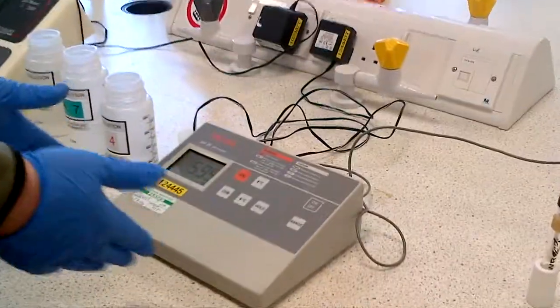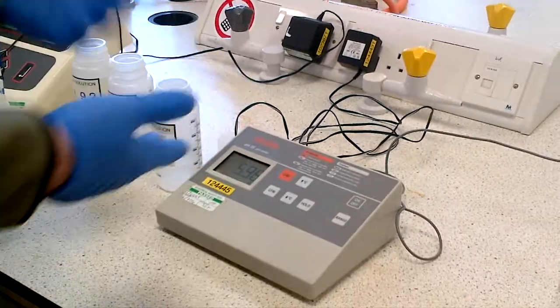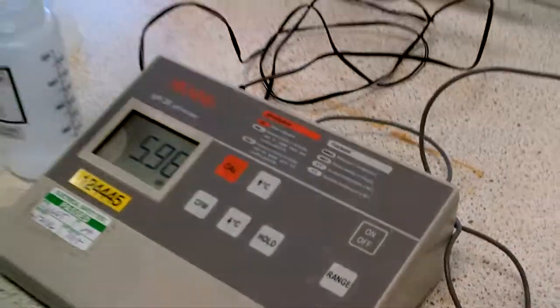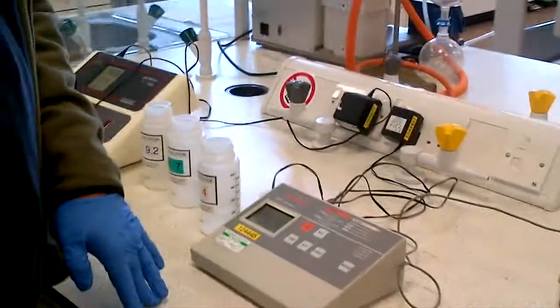Likewise with the Hanna one, again you need to calibrate it against buffer solutions, as we've shown, by pressing the calibration key, placing the electrode into each of the two buffers and following the instructions which are clearly represented on this box. So this is how to use a Jenway and Hanna pH electrode. Thank you.